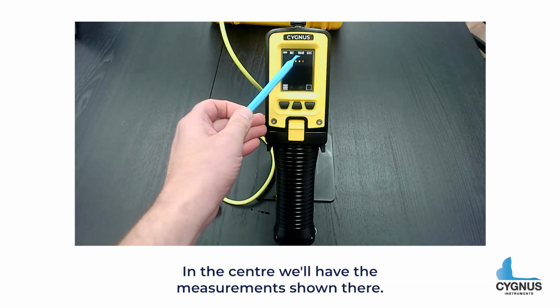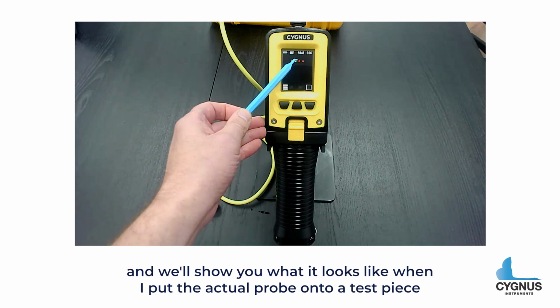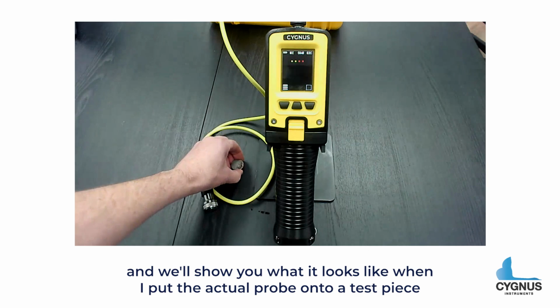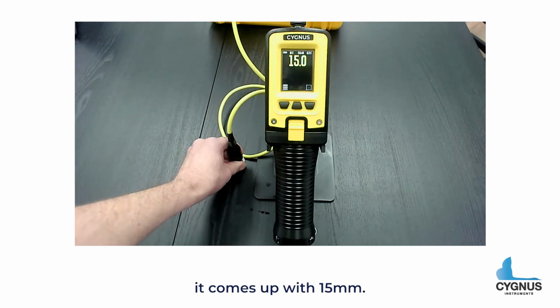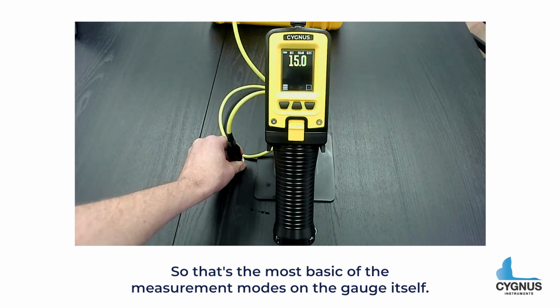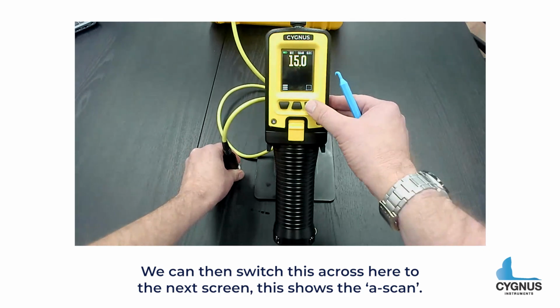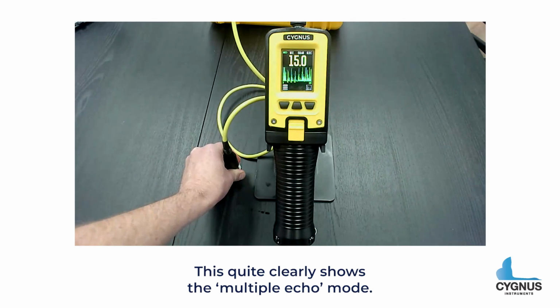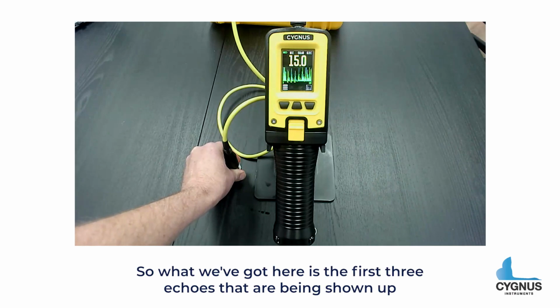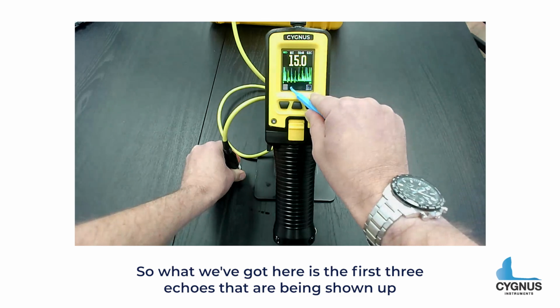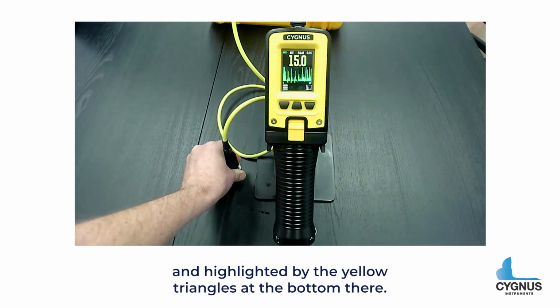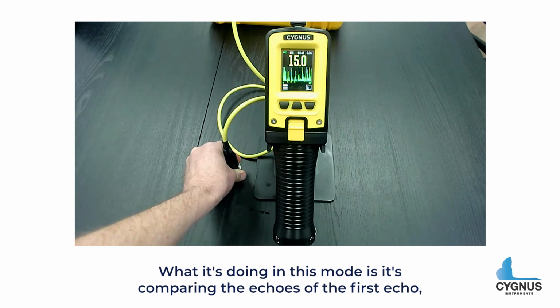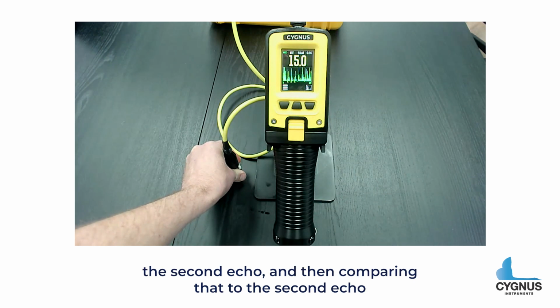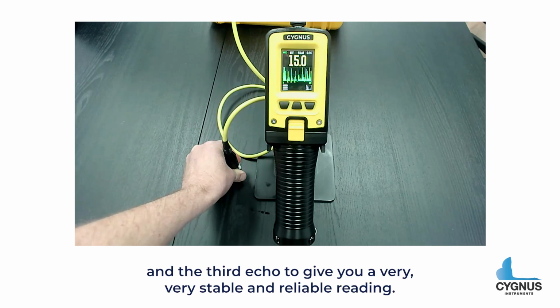In the center, we'll have the measurements shown there, and I'll show you what it looks like. When I put the actual probe onto a test piece, it comes up with 15 millimeters. So that's the most basic of the measurement modes on the gauge itself. We can then switch across to the next screen. This shows the A scan. This quite clearly shows the multiple echo mode. What we've got here is the first three echoes being shown and highlighted by the yellow triangles at the bottom there. What it's doing in this mode is comparing the first echo and the second echo, and then comparing the second echo and the third echo to give you a very, very stable and reliable reading.